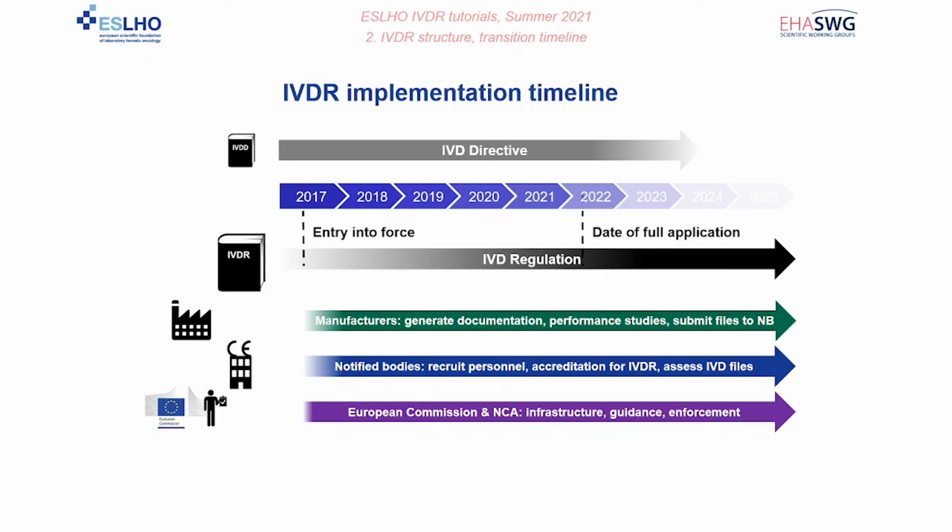In the meantime, the European Commission and the national competent authorities are working hard on the required infrastructure. For example, during the review of Class D devices, the highest risk devices under the IVDR, European reference laboratories and expert panels are involved. These are being set up. Also, all CE IVDs will have to be registered in a central medical device database called EUDAMED. This database is under construction.